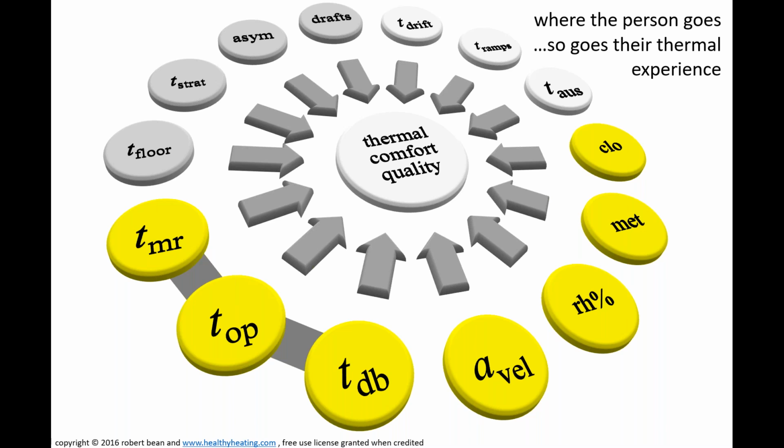And when you get the ingredients right, when the humidity is right and the air temperature and the mean radiant temperature is right, and you understand what they're doing and wearing in the space, and we control temperature stratification and floor temperatures and this asymmetry, that will have a much higher probability of people enjoying the space and not being stressed out by overheating and underheating. And this really ultimately comes down to what the objective of the standard is: to reduce the stress level associated with thermal discomfort. And we know, the studies tell us, that people get distracted by bad indoor environments. And in that distraction, they lose their productivity.